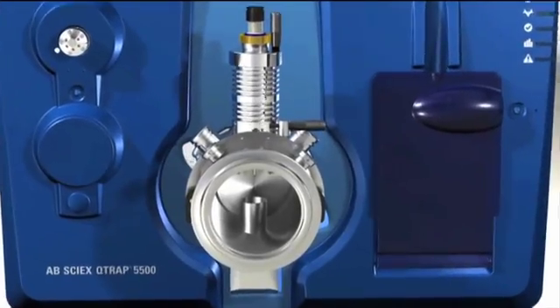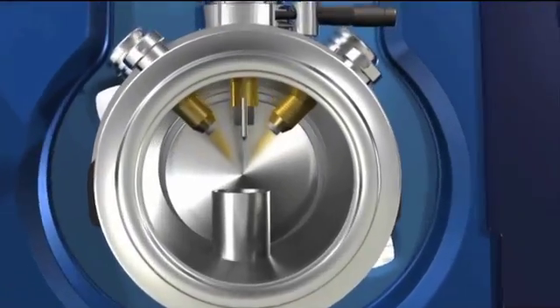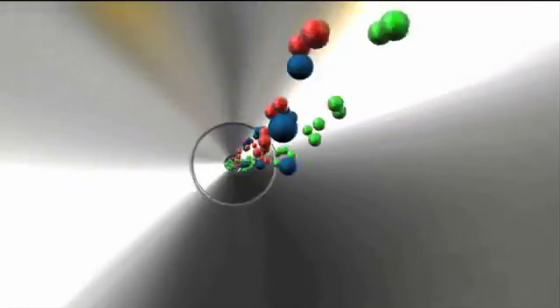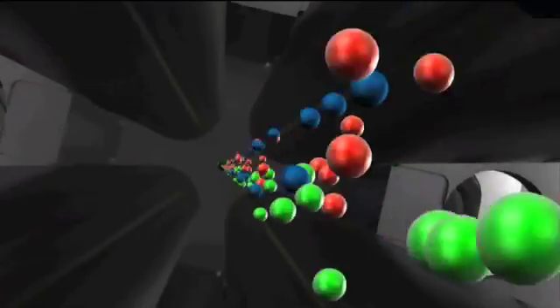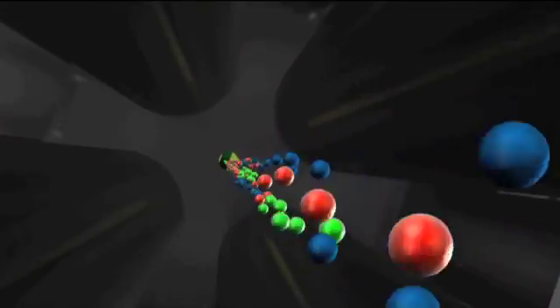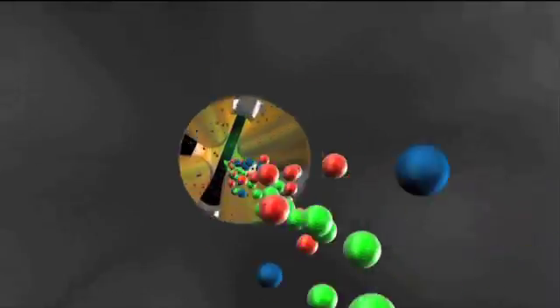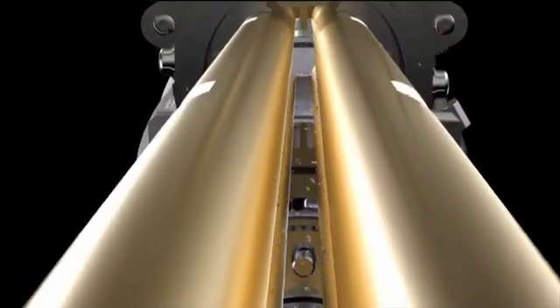Downstream from the industry-leading Turbo V-Source, the new QJET-2 ion guide further improves on patented collisional focusing to optimize transmission and give ultimate sensitivity. Following parent ion selection in Q1, the newly designed curved linac collision cell generates true database-searchable fragment ions and accelerates them into Q3 to eliminate crosstalk.